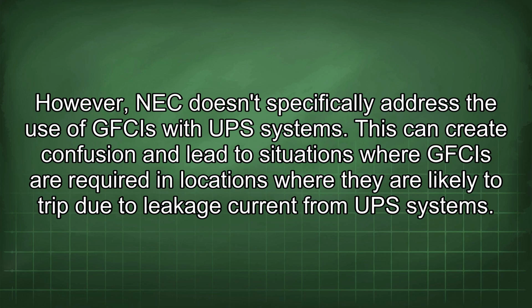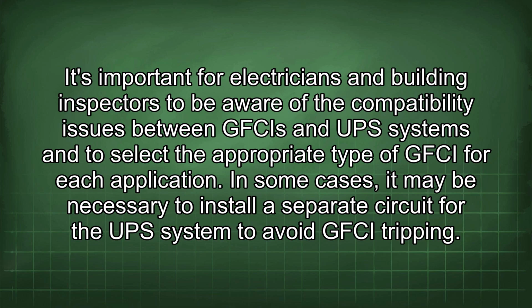This can create confusion and lead to situations where GFCIs are required in locations where they are likely to trip due to leakage current from UPS systems. It's important for electricians and building inspectors to be aware of the compatibility issues between GFCIs and UPS systems and to select the appropriate type of GFCI for each application. In some cases, it may be necessary to install a separate circuit for the UPS system to avoid GFCI tripping.